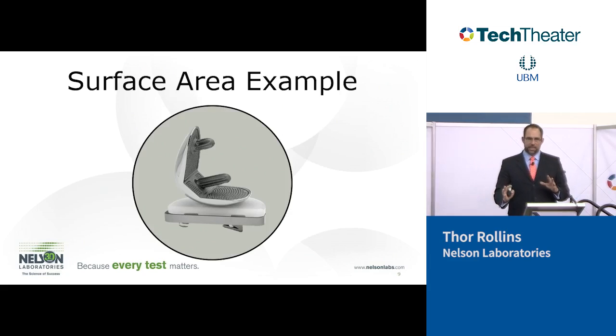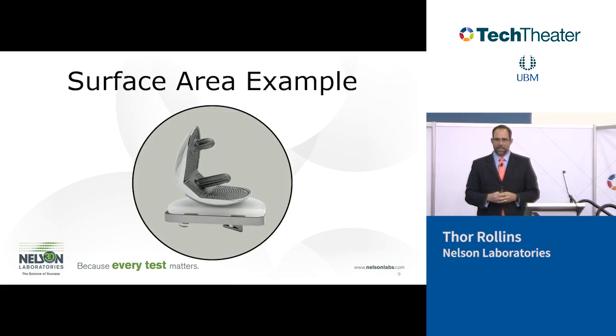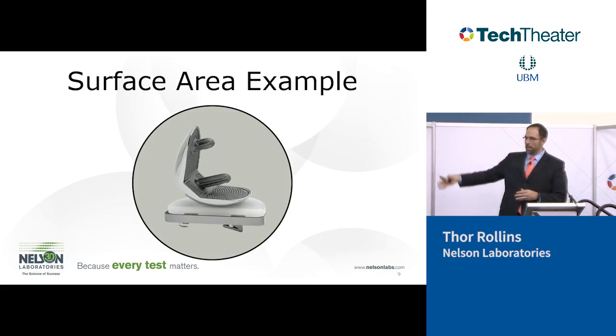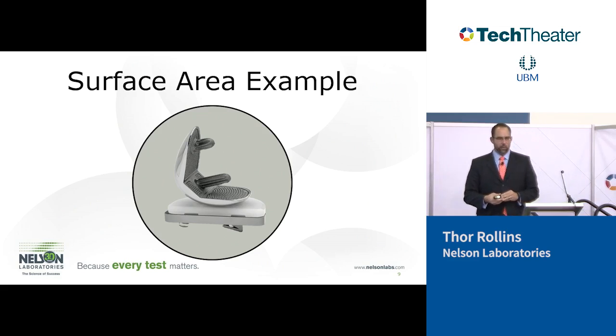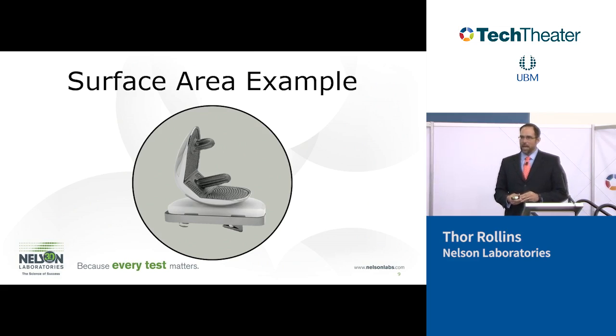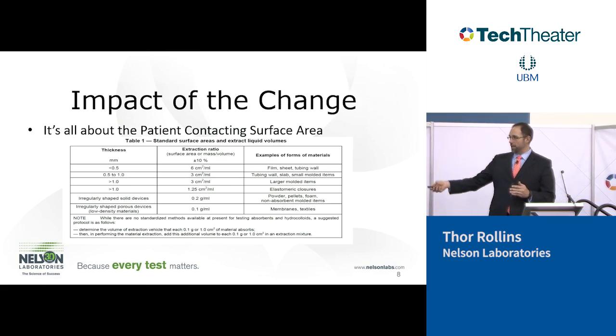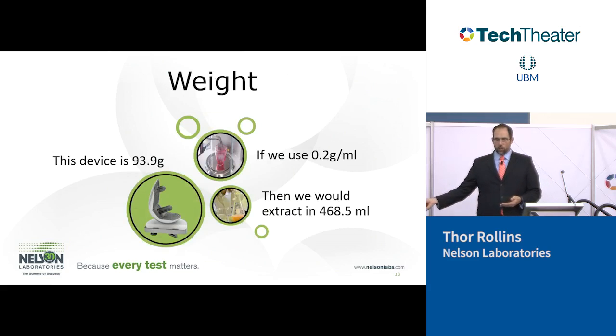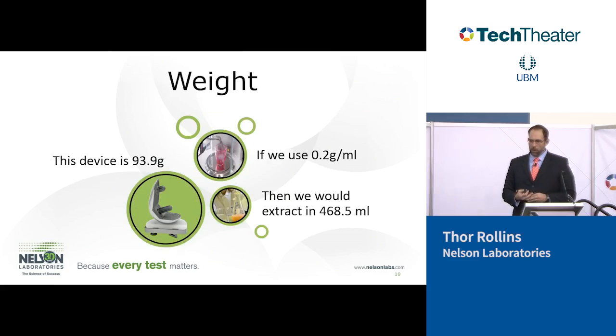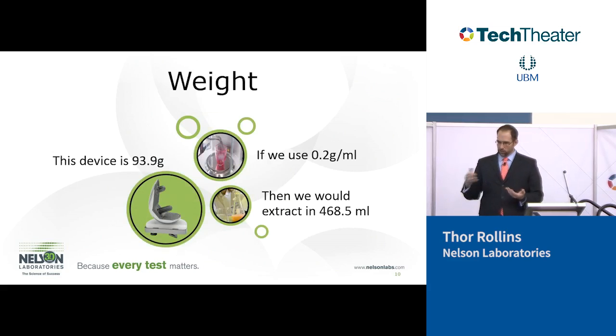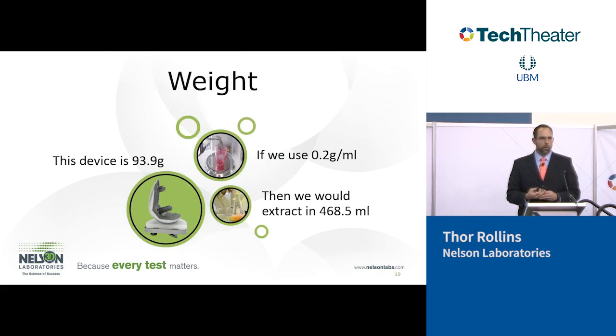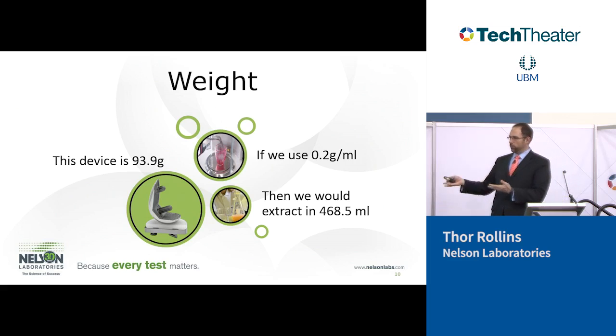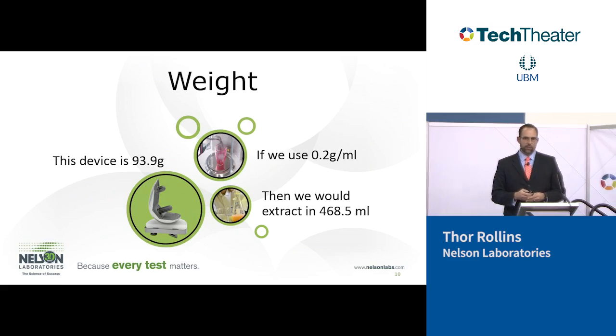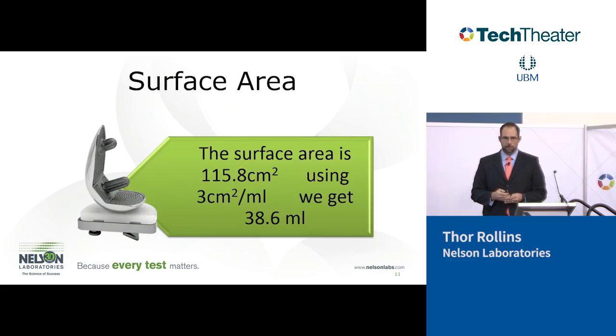To give you an idea about how the surface area plays a role in my testing, I'm going to give you an example. Right here is a partial knee implant. It's a very common medical device that we see a lot come in for testing. Per this chart, we have two ways we can test it, either surface area or weight, okay? By weight, this device weighs 93.9 grams. So per that chart I showed you, we would extract at 0.2 grams per mL. This would give us 468.5 mL of extraction fluid for this knee, okay?